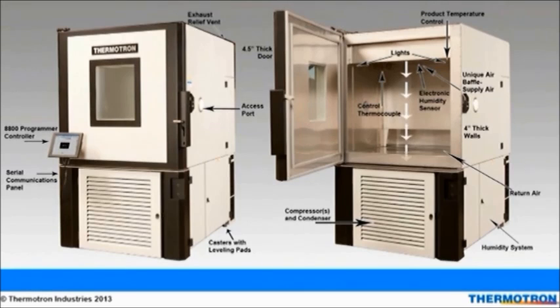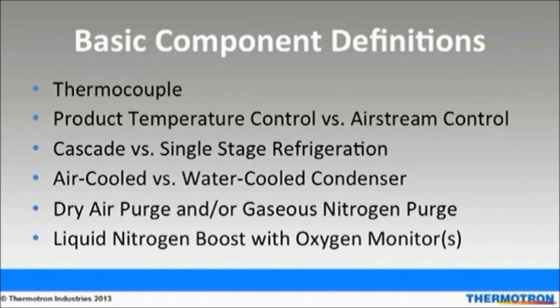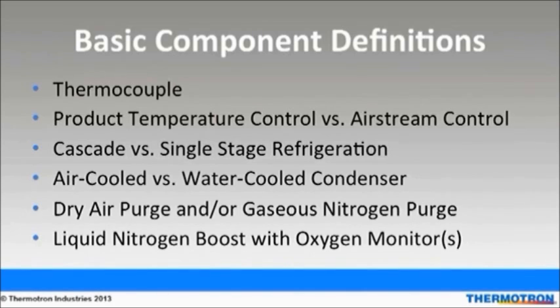The air returns from the chamber floor. The humidity system is located on the right side cabinet, and the compressors and condensers are housed in the front cabinet. A thermocouple is a movable device that measures temperature. Product temperature control maximizes stress on the product through the chamber's control system and optimized air flow. Airstream control measures the air temperature at the outlet source of the air supply. Product temperature control measures the product's temperature.